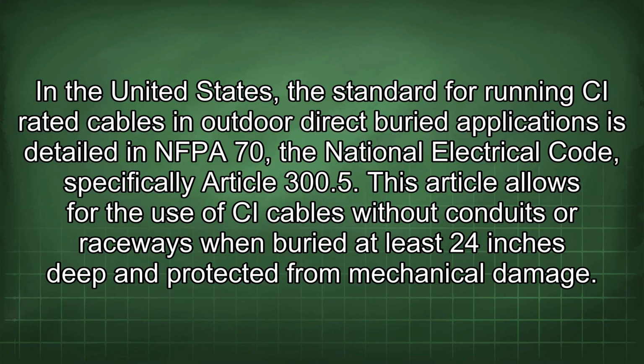In the United States, the standard for running CI-rated cables in outdoor direct buried applications is detailed in NFPA 70, the National Electrical Code, specifically Article 300.5. This article allows for the use of CI cables without conduits or raceways when buried at least 24 inches deep and protected from mechanical damage.